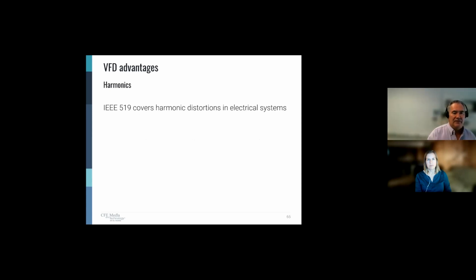And we have IEEE 519 to help us, okay? Covers harmonic distortions in electrical systems. This is something to pay attention to when you're specifying VFDs, is to make sure that the VFD is compliant with IEEE 519.